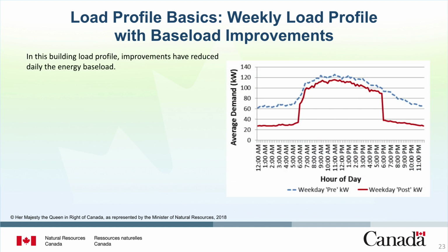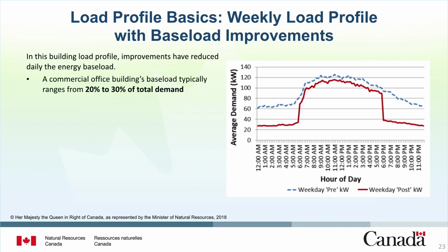Again, we use a weekday load profile as an example. In this building load profile, improvements have reduced the daily energy base load. The original pre-improvement load profile is denoted by the blue dashed line. This indicates a relatively high base load that equals approximately 50% of total demand. In contrast, a commercial office building's base load typically ranges from 20 to 30% of total demand. A base load higher than this range indicates excessive off-hour loads and should be investigated for efficiency opportunities.